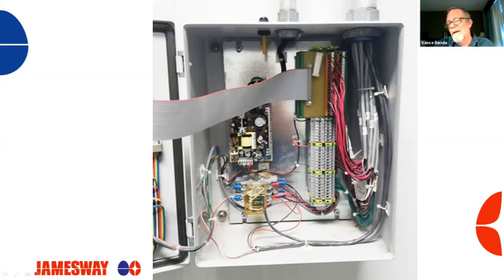Here are your thermostat wires going out. There'll be 16 of them. Two wires connected up here. All your whites are connected here, they're all jumpered together, and getting their DC negative right there. Here's all your browns, you're getting your DC positive, and they're all jumpered together. You always want to make sure to keep these little jumper screws tight. And then here's your ground. See the green wire coming in here? They're all jumpered together. And that's about all.